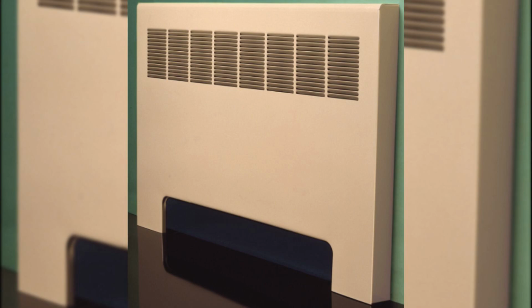B. Fully recessed ceiling-mounted electric cabinet heaters are to be used. C. In applications with heat pump units that generate hot water, fully recessed ceiling-mounted hot water cabinet heaters or fully recessed hot water convectors, mounted 4 inches above the finished floor, may be used. 3. Public assembly spaces. A. These spaces, when equipped with single-zone variable air volume (SZVAV) units, should be served by recessed perimeter electric convectors mounted 4 inches above the finished floor. B. If chiller heaters are provided, recessed perimeter hot water convectors should be used instead.